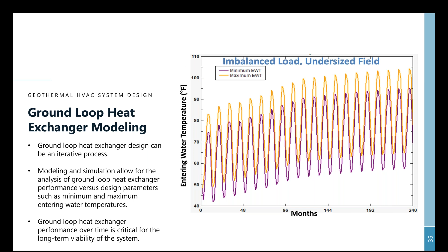The image that you're seeing on the screen now represents that imbalanced load that we discussed a little bit earlier. And really what you're seeing is that over time, you're getting a consistent elevation of the ground temperature. Now, in some cases, there is a range of ground temperatures that may be acceptable. But when you start heating up a bore field over time, you can get to the point where your equipment may not operate. The entering water temperatures may become too high to operate equipment during the cooling season. Or if the entering water temperature is still acceptable, you're going to have decreased performance. So again, one of the things that we look at when we're doing these iterations is how the bore field is performing over the long term.